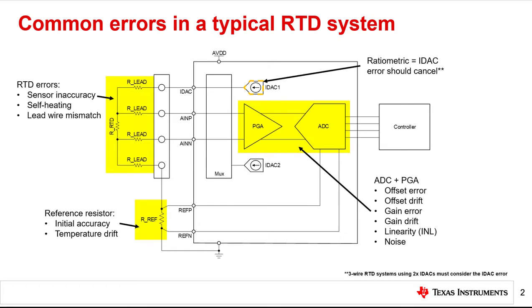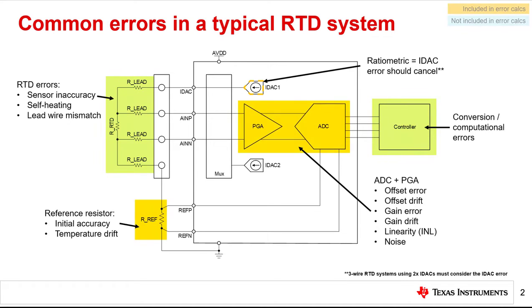The RTD itself can contribute error in the form of variation in sensor accuracy, self-heating, and lead wire mismatch. Finally, the controller can introduce computational errors in the resistance to temperature conversion process. While all of these errors are important, the total error calculations only include those errors that come from the signal chain — the ADC, PGA, and reference resistor errors, highlighted in orange. Errors from the sensor or conversion process are not included and are highlighted in blue.